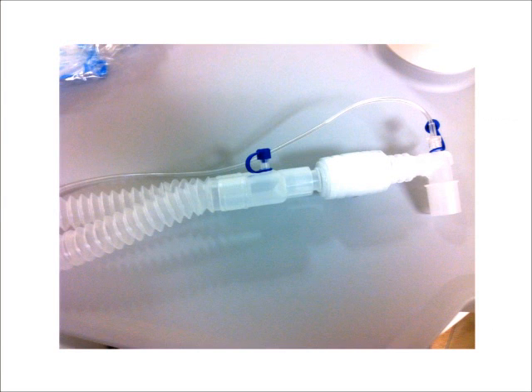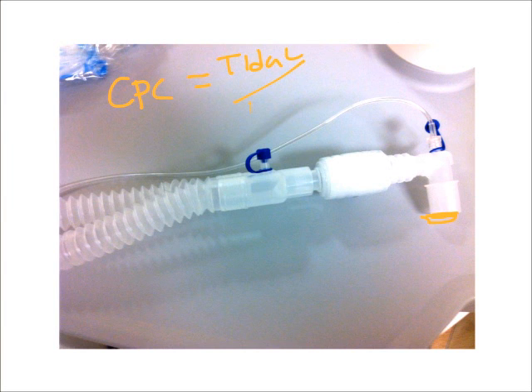So on older ventilators, how do we calculate the patient circuit compliance? So we know how much tidal volume is lost when we deliver a breath to a patient with each breath. Now, I haven't done this procedure for over 15 years. I'm used to ventilators that automatically do it. But how the ventilator does it is you will have to occlude the circuit. The compliance of my patient circuit equals the delivered tidal volume divided by my peak inspiratory pressure minus my PEEP.